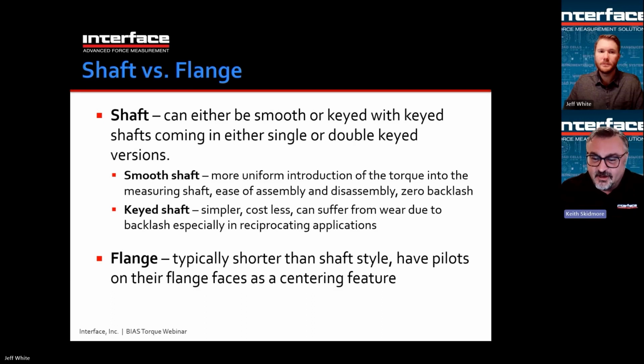Flange style sensors are typically a lot shorter than a shaft style, and they have pilots for centering. So whenever you're attaching rotating elements together, there should be features that allow them to be concentrically located one to the other. So flanges will have pilots for that. Like I said, they're quite a bit shorter. In test benches, a lot of times test bench real estate is at a premium, so a shorter drive line can be desirable. Next slide, please.